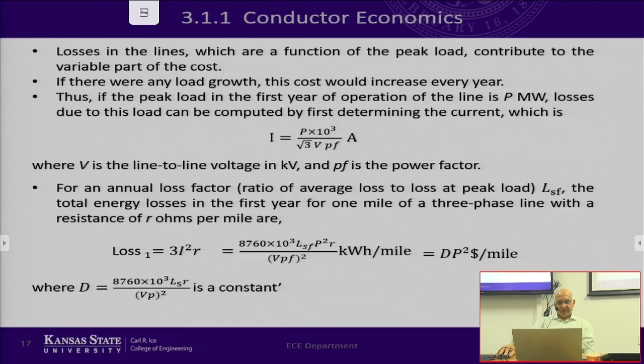Then we assume the load grows at a rate of M per year, so Pn, the load in any given year N, grows at rate M. The losses then grow at the square of the power, since we had talked earlier that current is proportional to power, so I squared is proportional to P squared. If P increases by a certain amount, the losses increase by the square of that amount. So losses grow as D times P sub N squared, which is D P squared times (1 plus M) raised to the power 2N. When you expand this, you find that the losses grow at the rate of M squared plus 2M.